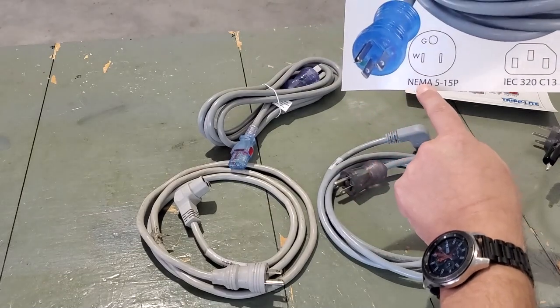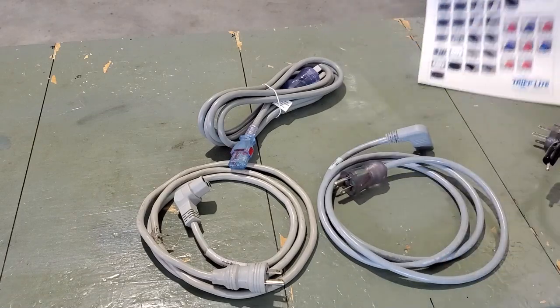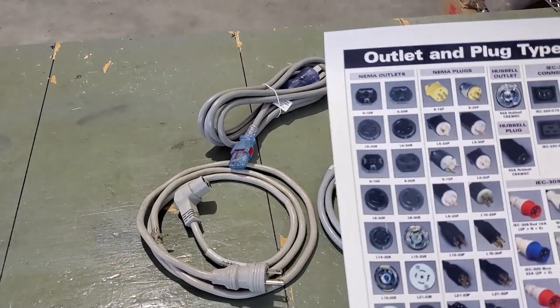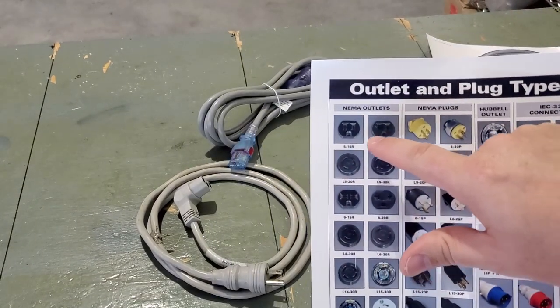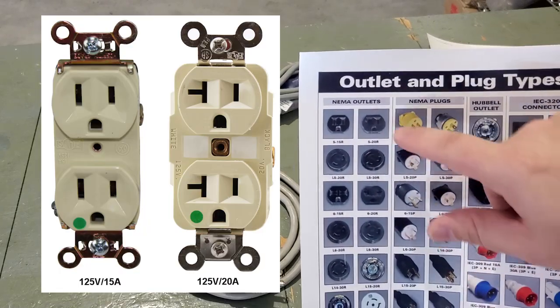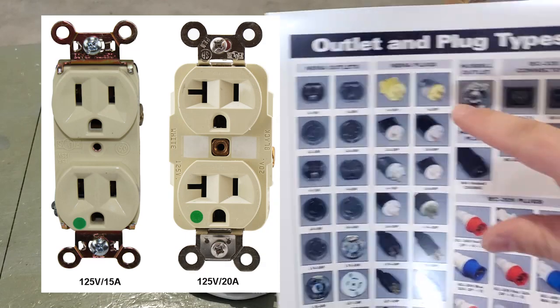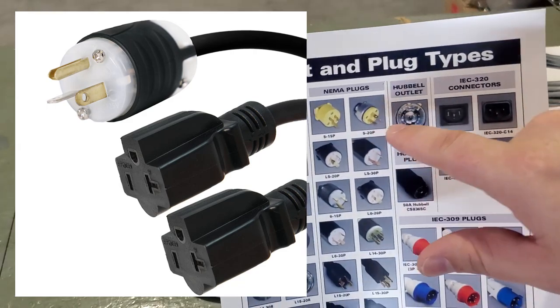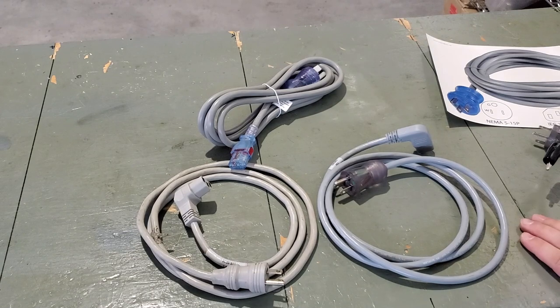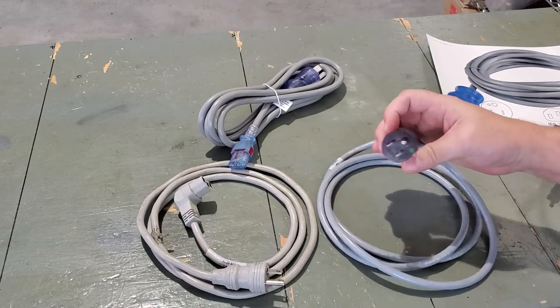The other style you might see is a 5-20P, and that is going to have one of the blades in a horizontal position. Your voltage and amps are governed by the plug end. The traditional outlet you normally see is the 15-amp, but there's also a 20-amp — the outlets found in medical facilities — which has a little horizontal piece along with the straight piece. The corresponding plug is called the 5-20P. You'll find these usually on heater coolers, refrigerators and freezers — things that pull a lot more current than traditional medical equipment.